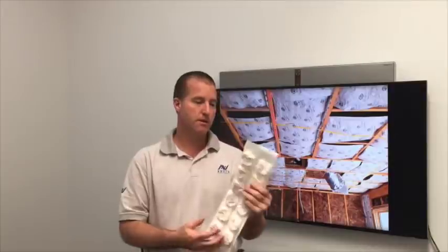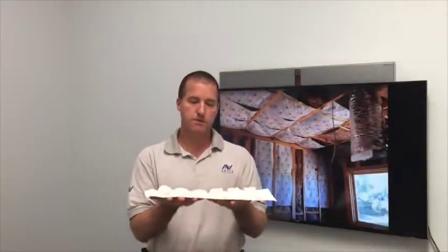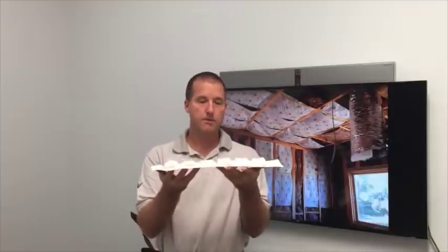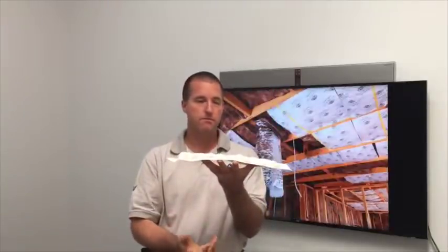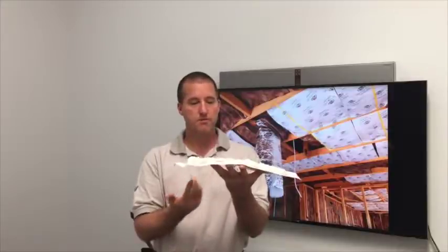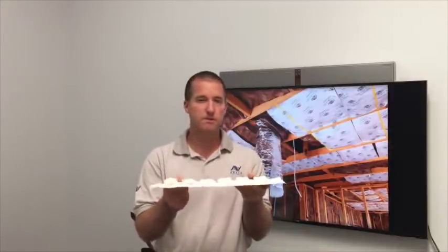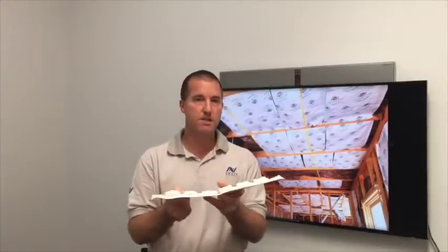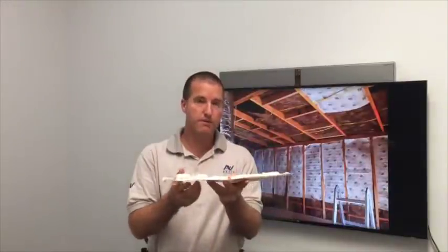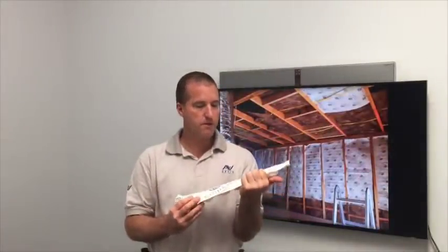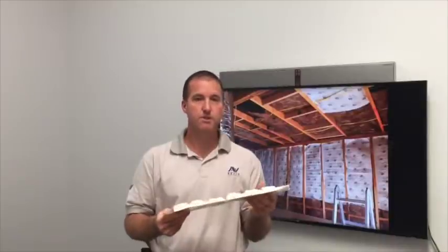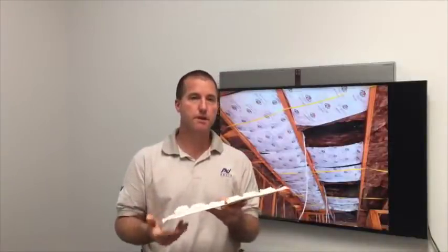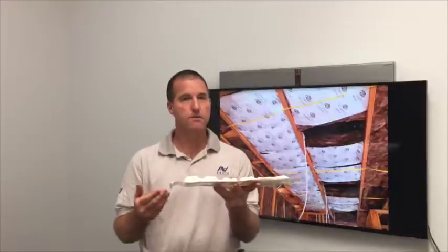And what that means is, if we put this material inside a ceiling space of a building and we put an electric heater on inside that room, if you had, say, 20 square metres of this material, and it's about 300 watt hours per square metre, that's going to need about 6 kilowatt hours of heat to actually heat it and melt it, and to fill it up with energy. So the long and the short of it is, the more phase change material you put in the building, the longer it takes to get the building up to temperature, and the longer it takes to get it down to temperature again. So different types of phase change material give you different kinds of outcomes.